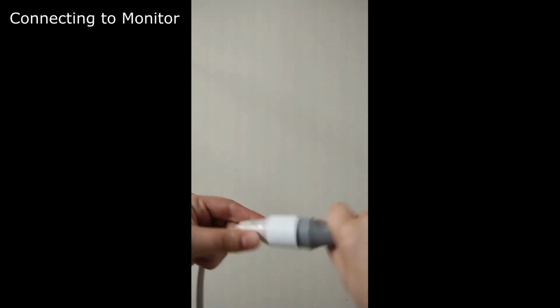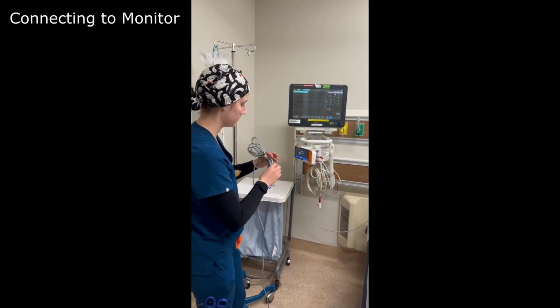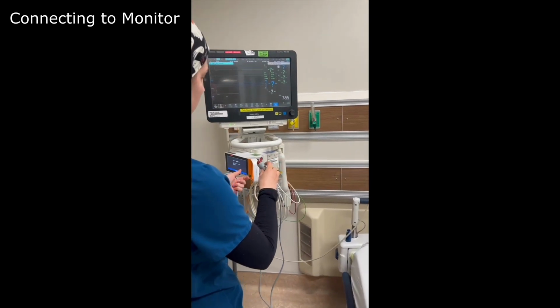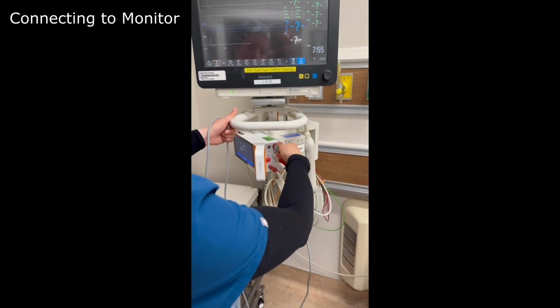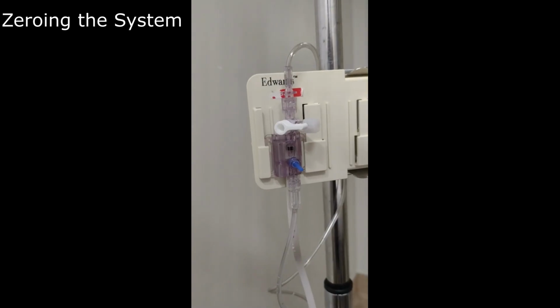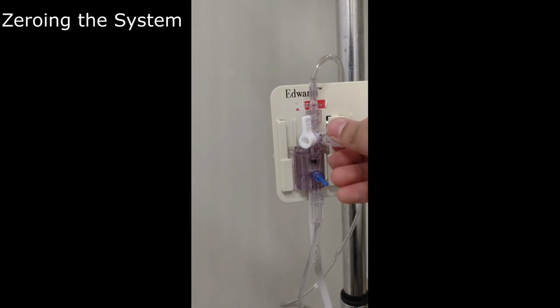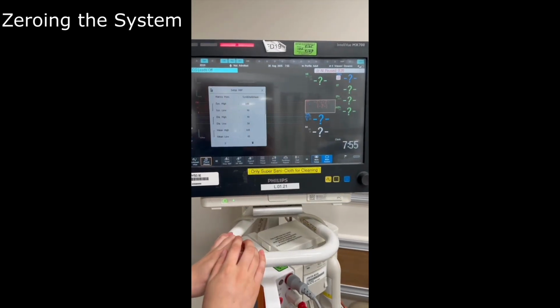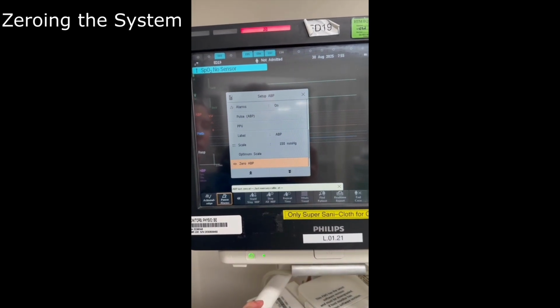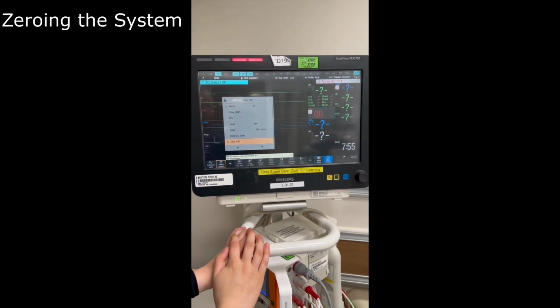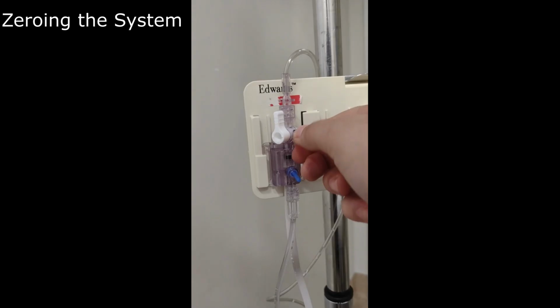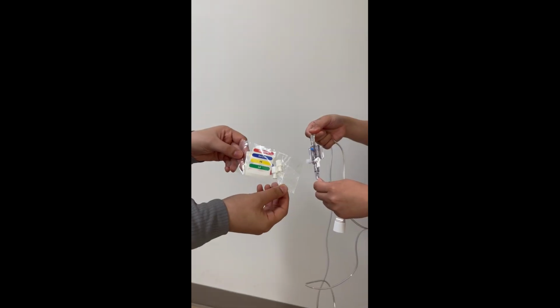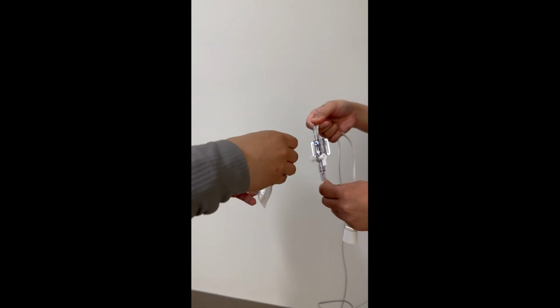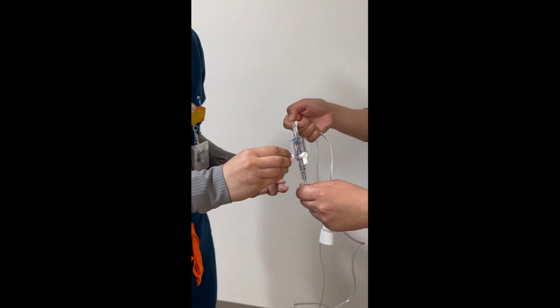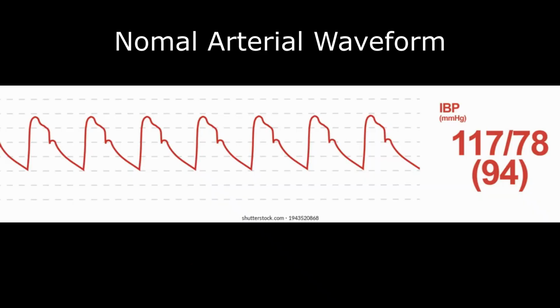Connect one end of the pressure cable to the port on the arterial tubing, and the other side connects to the box on the Philips monitor. To zero, turn the stopcock off toward the patient side and remove the cap open to air. This reads atmospheric pressure, so we can zero the art line on the monitor before replacing the cap and returning the stopcock off to air in the neutral horizontal position. At this time, you can also replace the vented cap with the white non-vented cap provided in the kit to maintain a closed system. Now, when connected to the monitor, you should see a normal arterial waveform as shown.